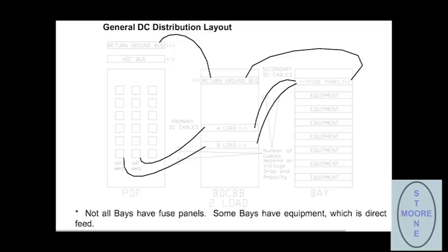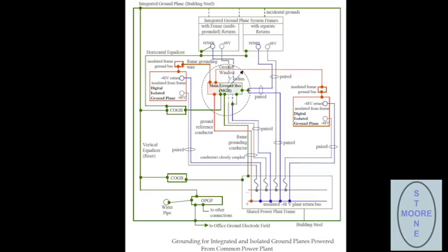The building steel, you don't want things with big differences of potential that could hurt somebody. So by bonding all of those things together, building steel, the DC plant itself, the main distributing frame in a wireline office, most transport equipment, everything else, door bucks, window frames, plumbing, HVAC equipment, all that stuff is all at the same potential as building steel. So they tie all of that together in addition to the frameworks of all the frames, and that's what's called the integrated ground plane.